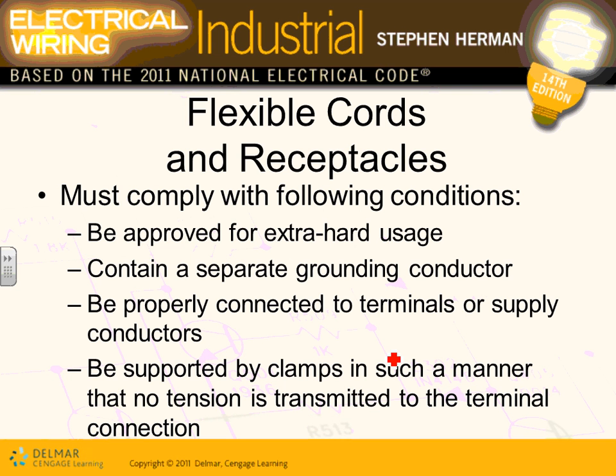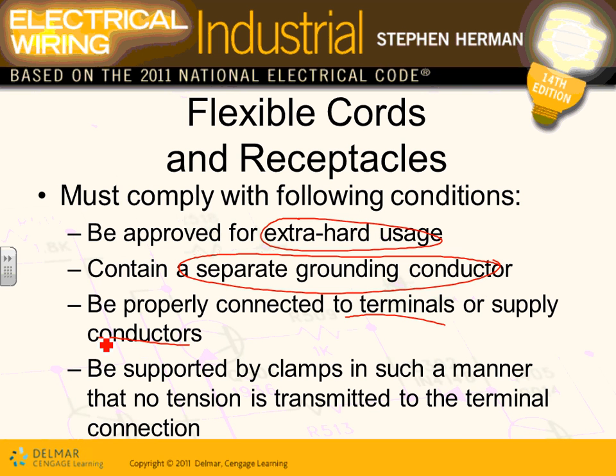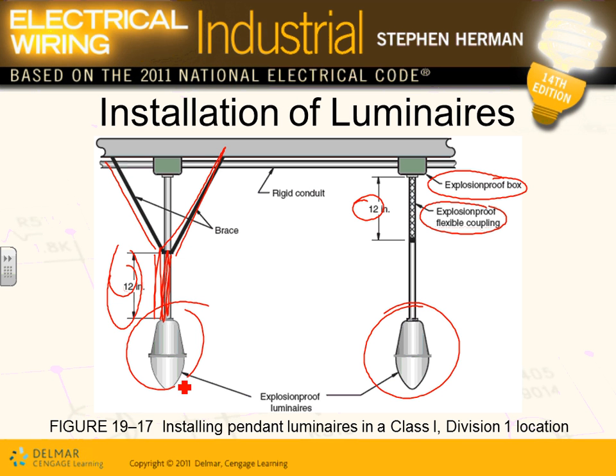Flexible cords and receptacles must comply with the following. If you have cords and receptacles, they have to be extra hard usage and explosion-proof. Your flexible cords must contain a separate grounding conductor, properly connected to the terminals. They have to have a proper connection so you don't put stress in the connectors. They must be supported by clamps in a manner that does not transfer the tension into the terminals. As you can see right here, as you put your cable in here, you don't want the weight of the whole system to transfer into the connection and arc and spark.